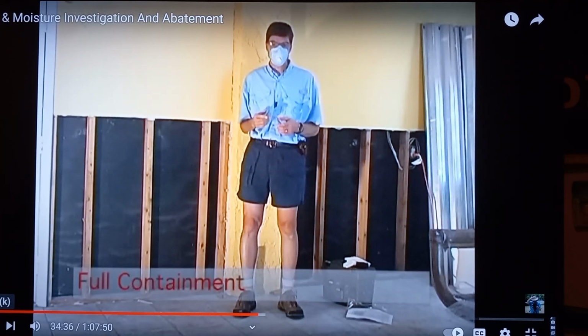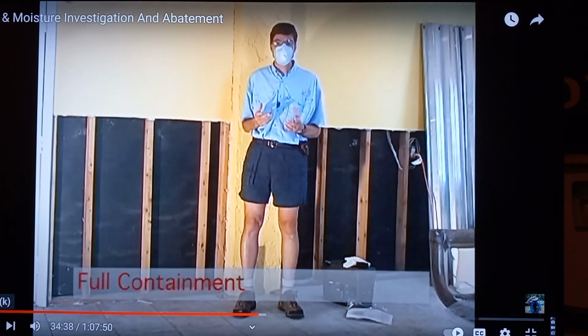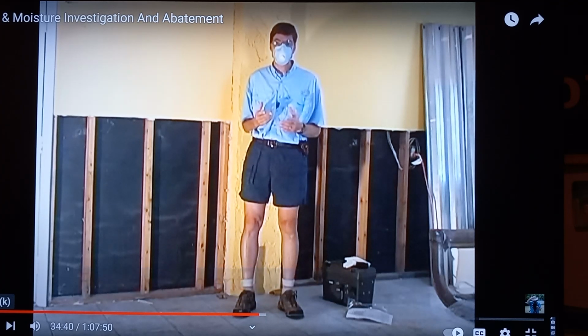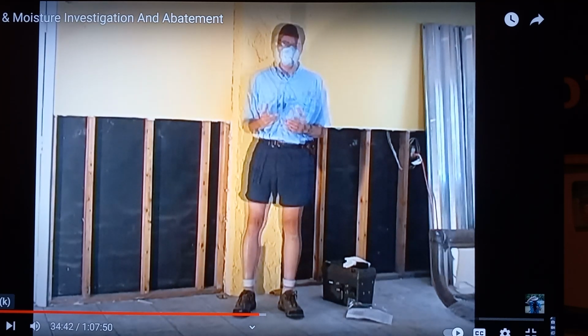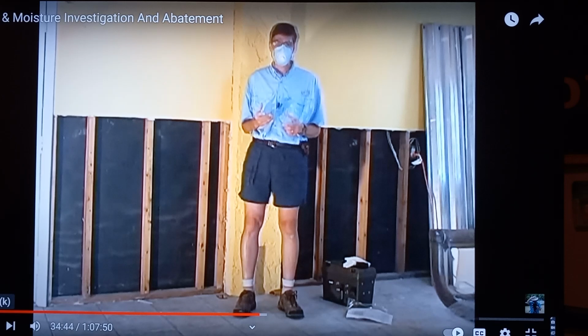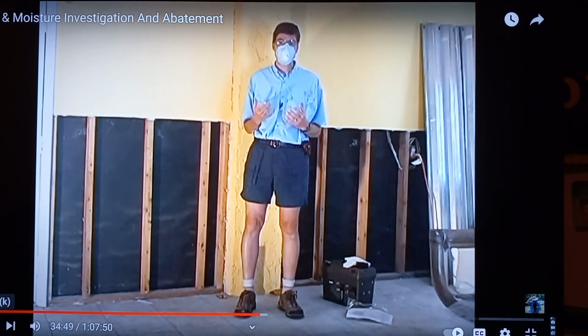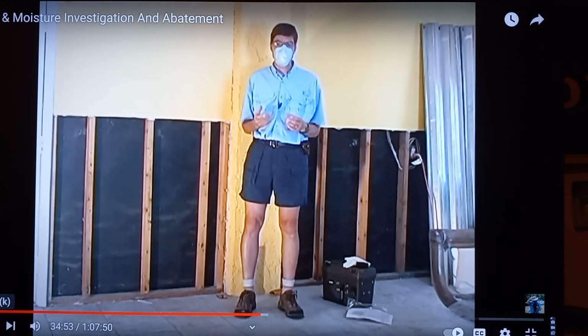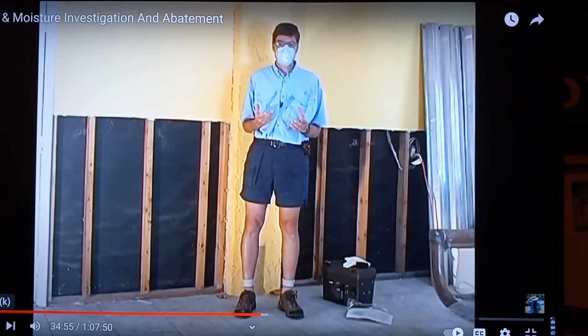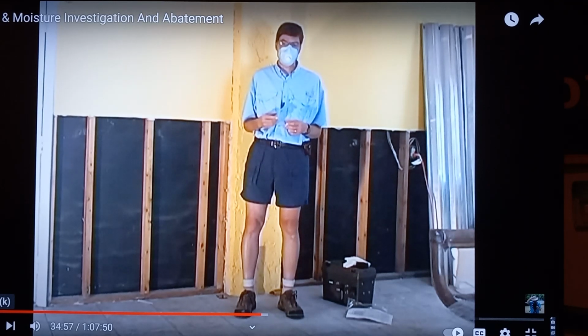Full containment would include use of 2 layers of fire retardant polyethylene sheeting with 1 airlock chamber. Maintain area under negative pressure with HEPA filter fan exhausted outside the building. And block and seal off air vents in containment area.